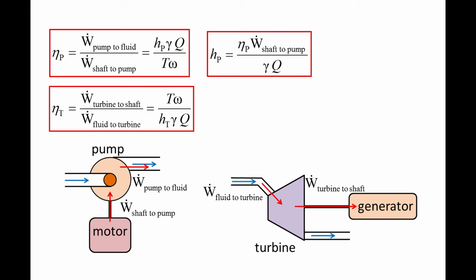The power transferred from the turbine through the shaft is the shaft torque times the shaft's angular speed. The power transferred from the fluid to the turbine is equal to the turbine head, HT, times the specific weight, times the volumetric flow rate.